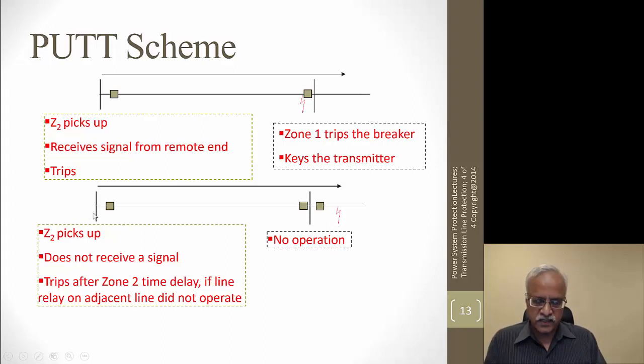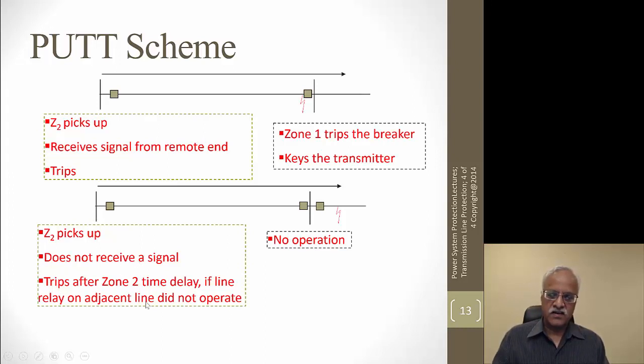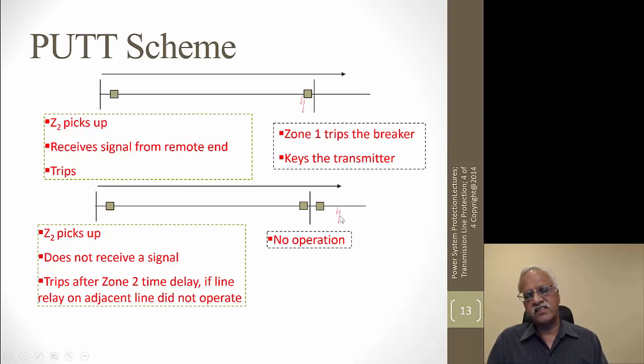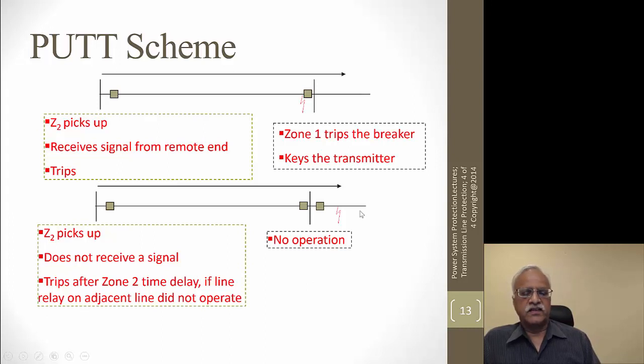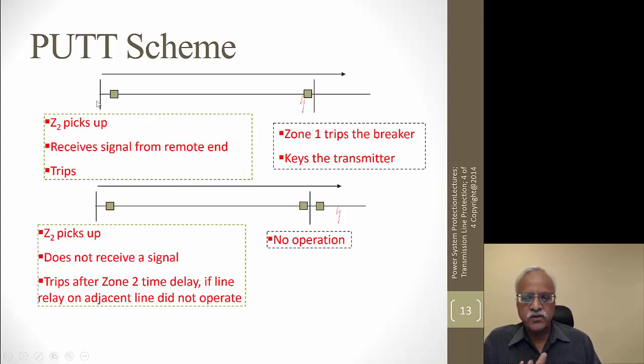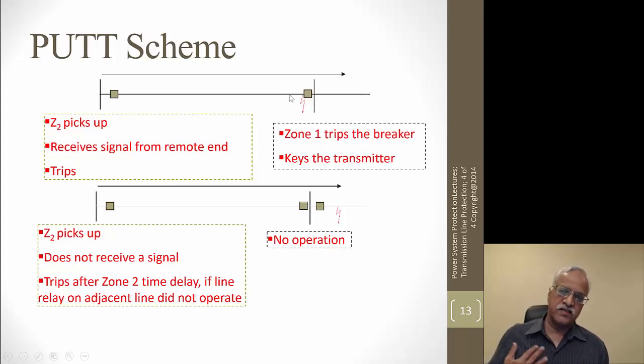If no signal is received, zone 2 picks up but trips only after its time delay — because it has not received a remote signal. This is also the backup behavior: if there is a failure of the signal, it operates on zone 2 time delay. So for a fault within the line section, the local end trips faster, while the remote end trips after a time delay if it does not receive a signal.